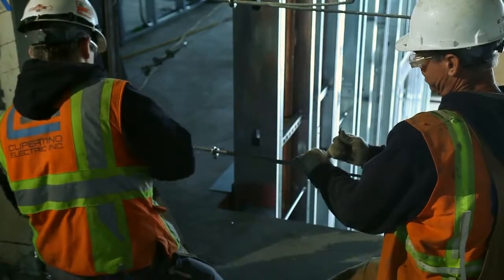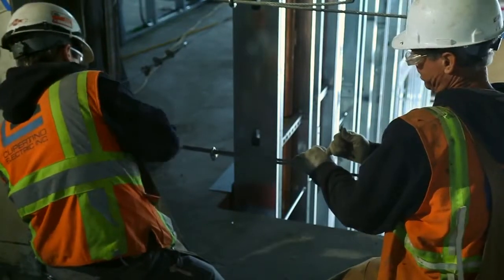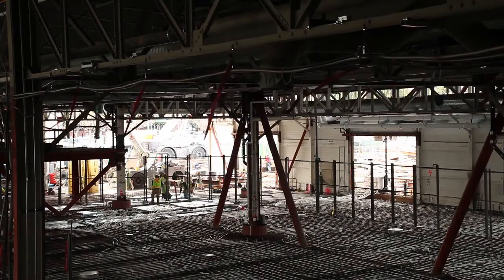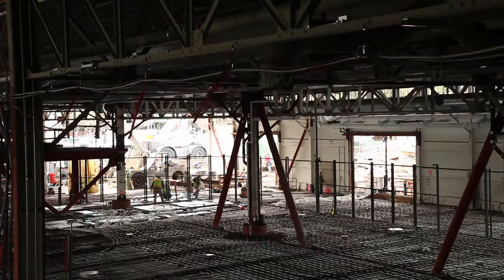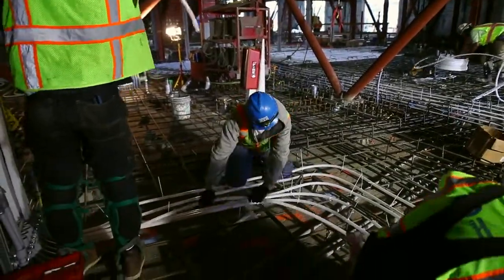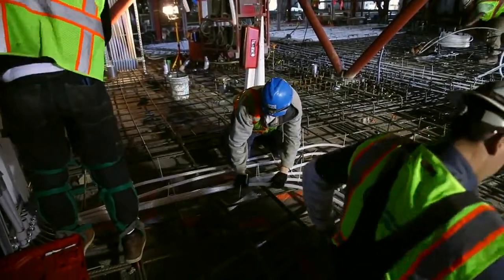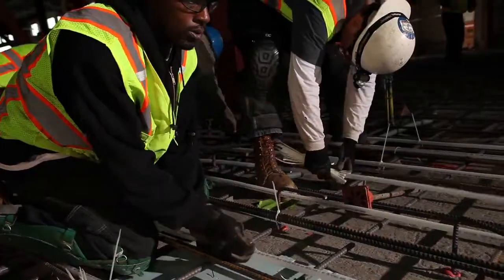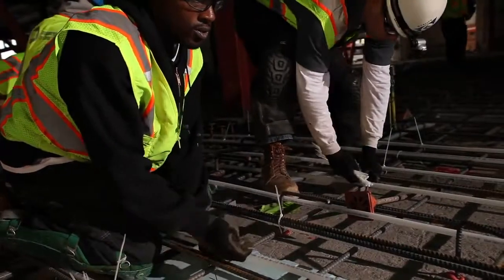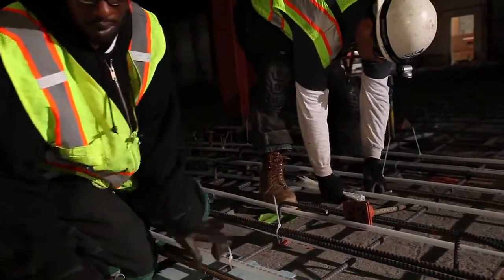Because of the need for earthquake protection, the first level of the building was more complex, consisting of 2 layers of rebar with the PEX loops positioned between and fastened to the lower stratum. The tubing sits 3 to 3.5 inches beneath the surface to avoid being punctured by anchors securing the museum's exhibits.